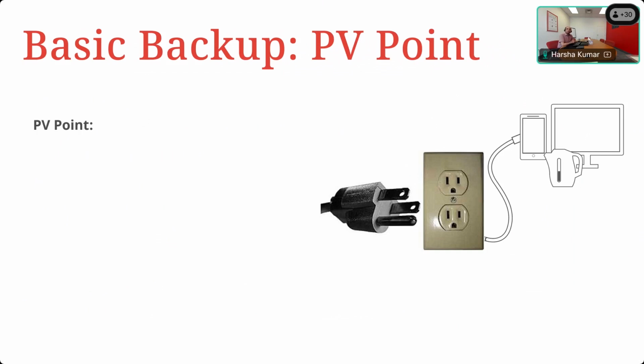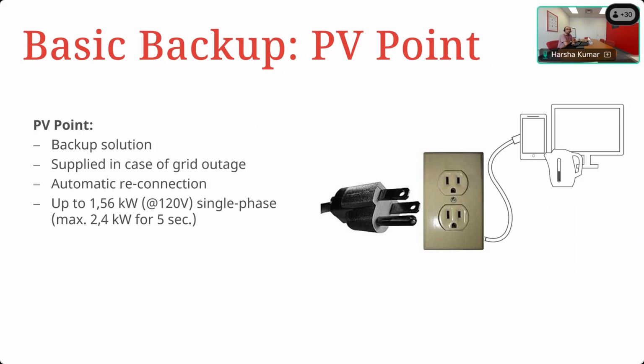So if you have any emergency loads, or want to charge your cell phone during an outage, the PV Point is your go-to. Please keep in mind the PV Point cannot be wired into your AC panel board or breaker panel - that's a violation of code. It needs to be wired into a separate receptacle by itself, and if you need protection, you'll need a circuit breaker there too. Again, this is only active when hydro is down; the moment hydro comes back, it becomes inactive. You don't need batteries for this to work - as long as you've got daylight and hydro is down, it's active.